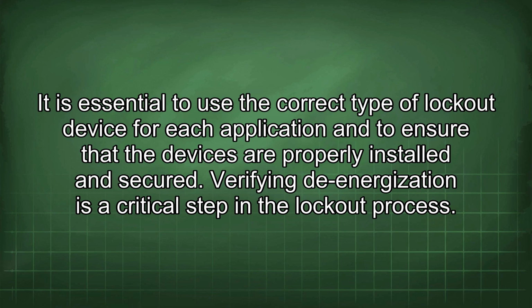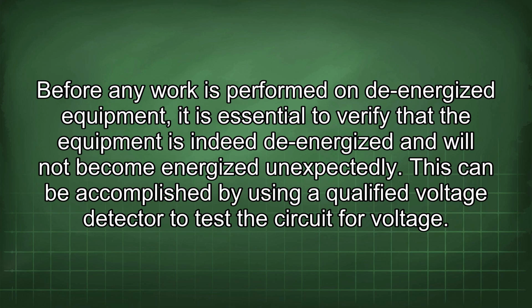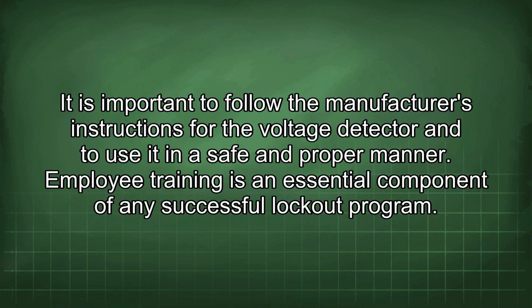Verifying de-energization is a critical step in the lockout process. Before any work is performed on de-energized equipment, it is essential to verify that the equipment is indeed de-energized and will not become energized unexpectedly. This can be accomplished by using a qualified voltage detector to test the circuit for voltage.